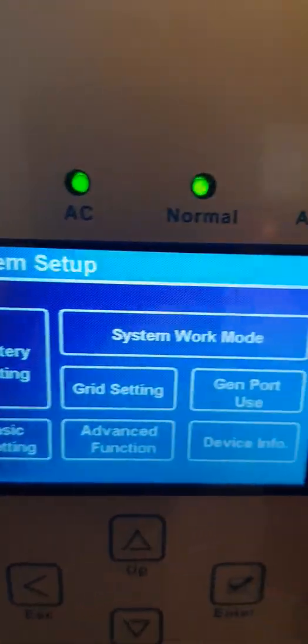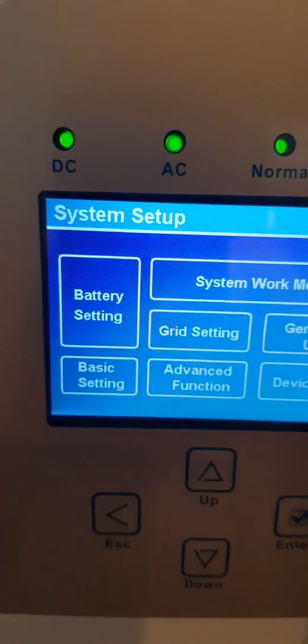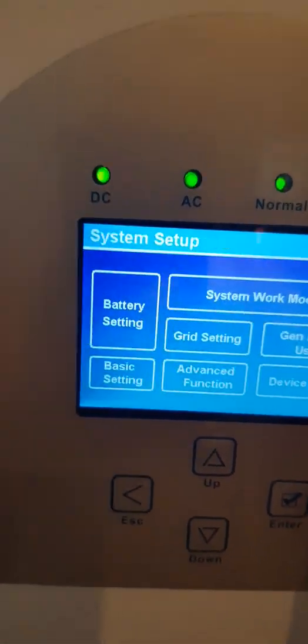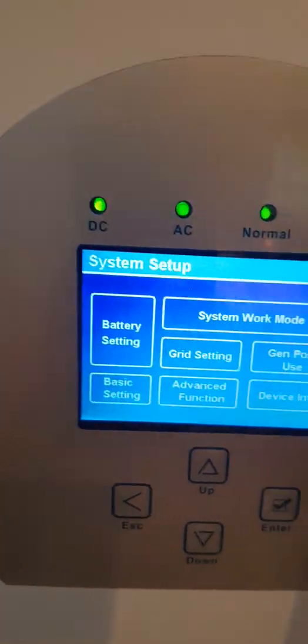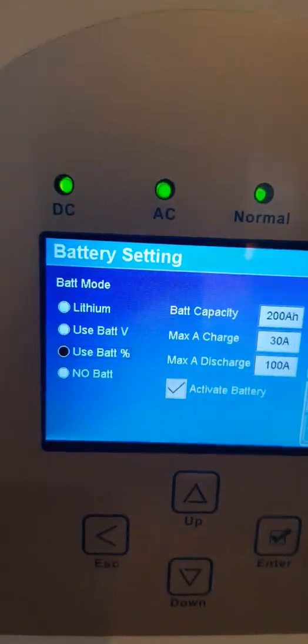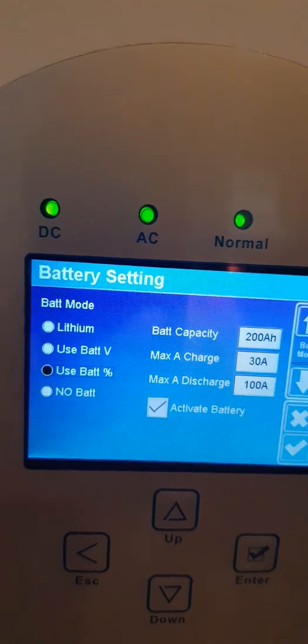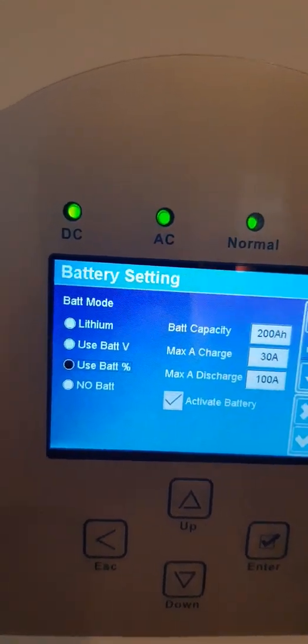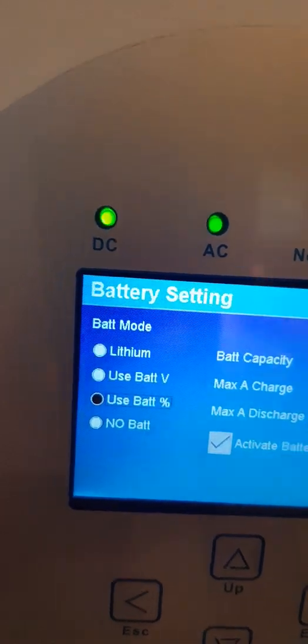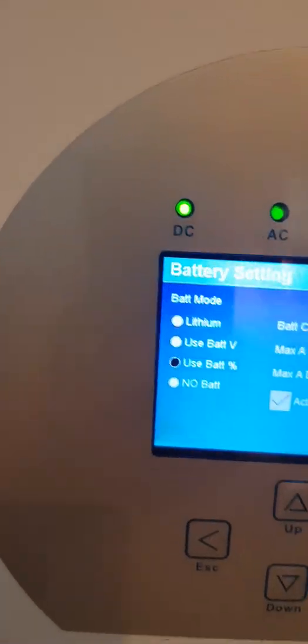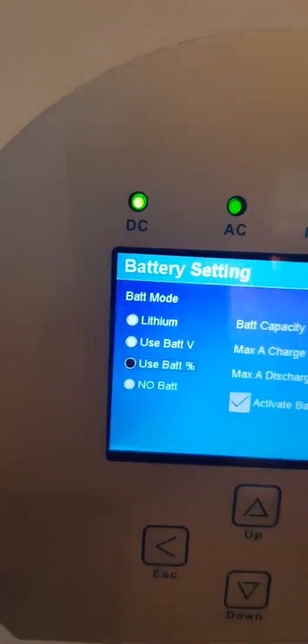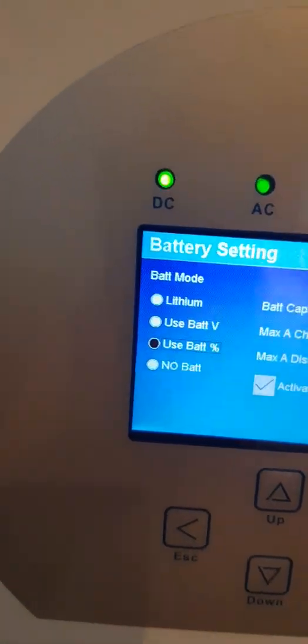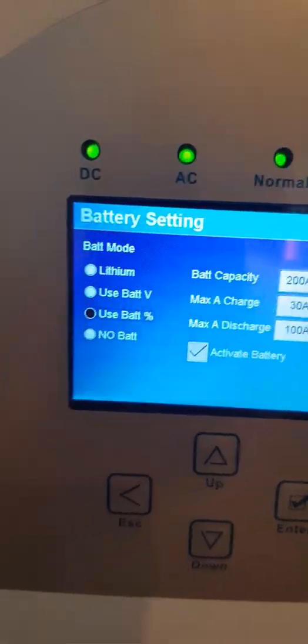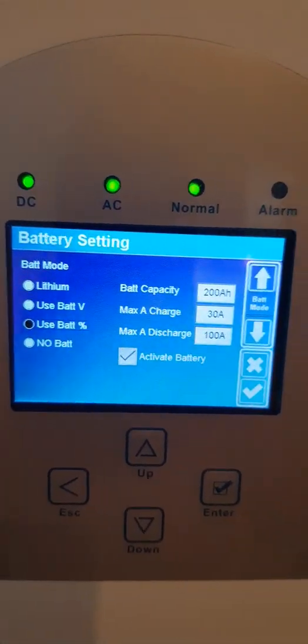Now we press on the setup. This is battery settings, system work mode. So basically, these are the only two options that we will be tackling. So first is the battery settings. Currently, the battery has no communication ports. That is why we use the battery percentage, or we can also use the battery voltage. But it is better to use the battery percentage, so it's easier for the inverter to choose whether to switch back to battery or use the energy from the grid.